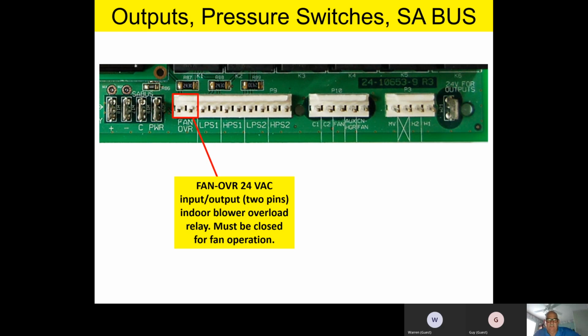FAN-OVR is a fan overload. Now this is something kind of unique. You're going to notice that on our Champion equipment, on our commercial equipment, we're going to have another little set of wires coming off the indoor blower motor. They're typically, I think they're purple wires if memory serves me. But they go to this fan overload, and what it is, it's an indoor blower overload relay. And it's a safety device, and it has to be closed for fan operation.